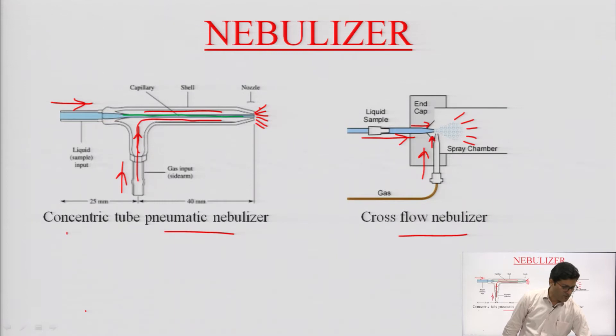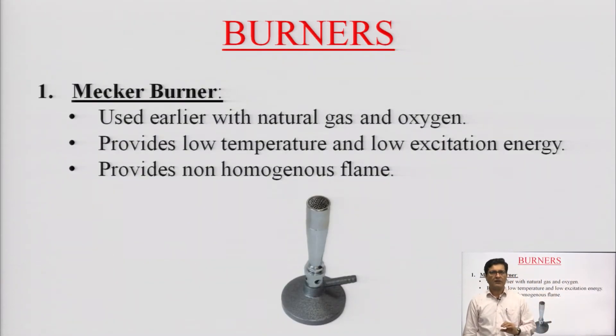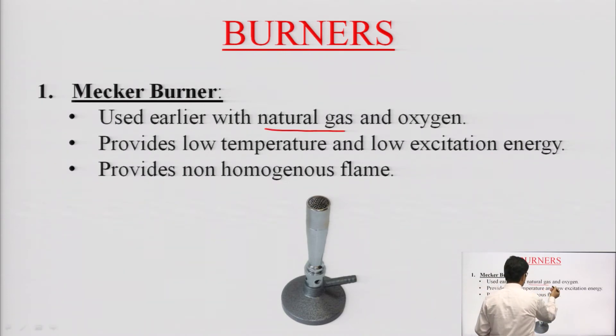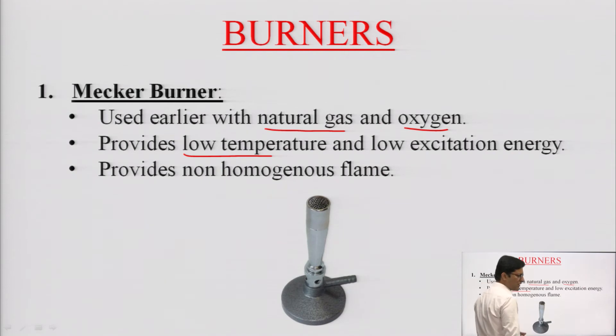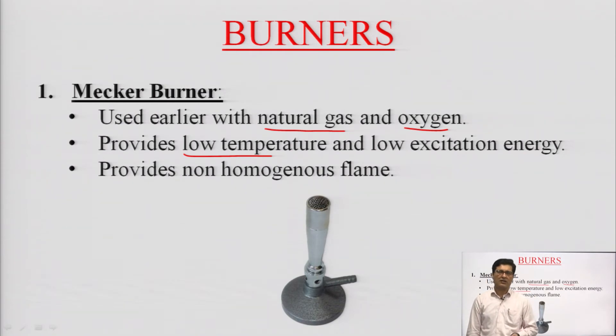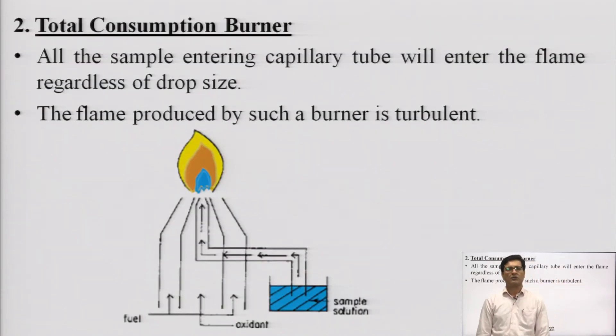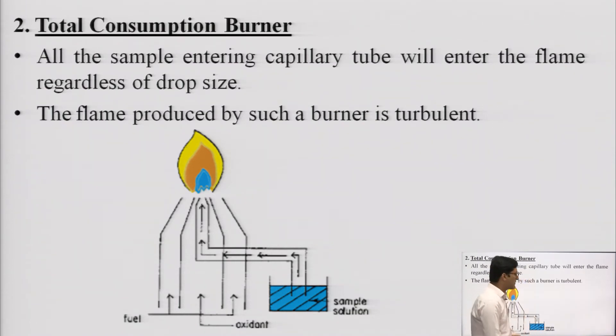Regarding the burner component, the first type is the Mecker burner, which is outdated and previously used. It generally uses natural chemical gas with air or oxygen, giving low-temperature flames and low excitation energy. The major drawback is that it provides a non-homogeneous flame with low energy, so maker burners are now obsolete. Primarily, two major types of burners are used: the total consumption burner and the premix burner.